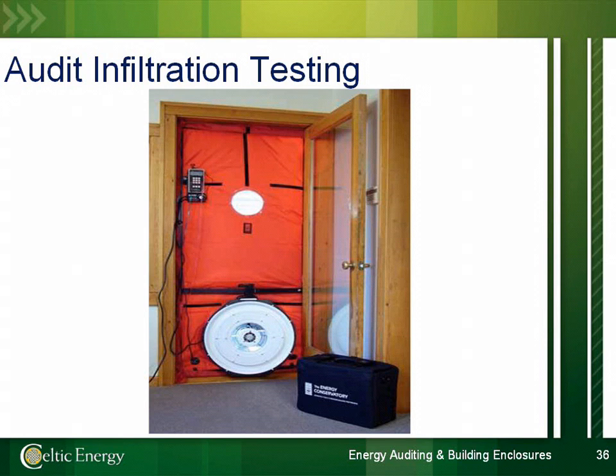Likewise, this technology can be very effectively combined with infrared technology, because if you perform an infiltration test in a building, again, it doesn't have to be the whole building that's done at once. You might do, as I mentioned, a floor-by-floor approach. If you do this on a day when there's a significant temperature difference, at least 10 degrees between inside and outside, and you use an infrared camera, sources of air leakage will be illuminated and you can quickly pinpoint the physical location of them. Guided air sealing can be performed very effectively using these two technologies to document, locate, and correct infiltration in the building.